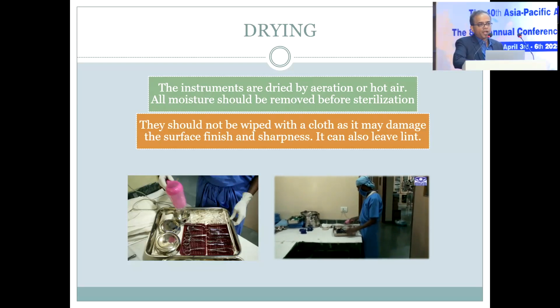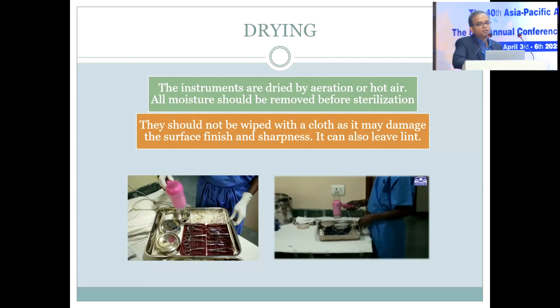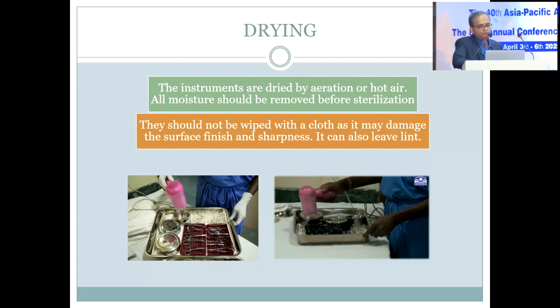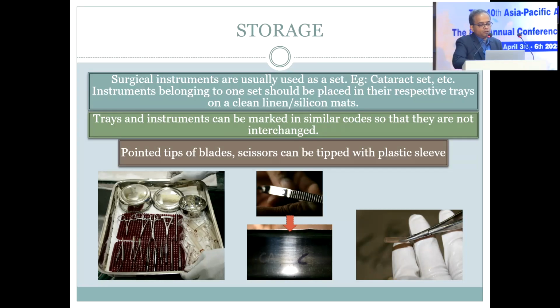Now coming to the drying part, which as I said is very important, because humidity will lead to immediate onset of growth of organisms. The instrument should be dried by aeration or hot air. This is very important, so that no humidity remains on the instruments before it goes for sterilization. It should not be wiped with a cloth or something, because that will lead to removal of the surface coating and blunting of the instruments.